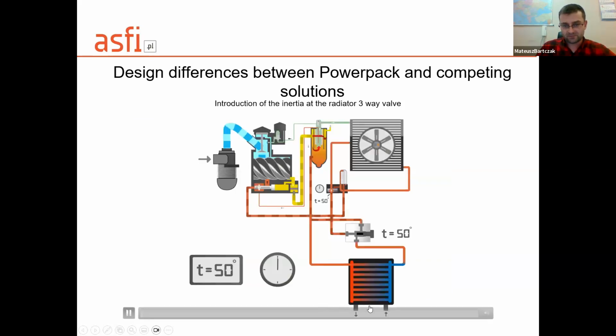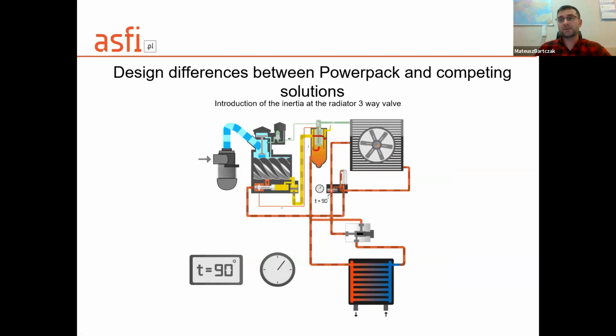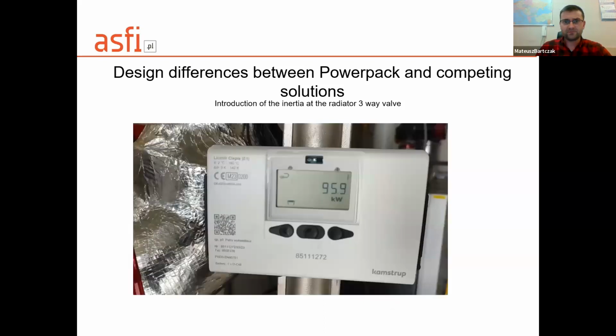Oh, I have to go back. In that case, if this valve doesn't have enough time to open, oil could flow to the injection valve on the short circuit without the oil cooler, and the compressor could be overheated. It's not an impossible situation. I will show you it on some recordings of our implementation. In this video, the heat meter shows this in practice.